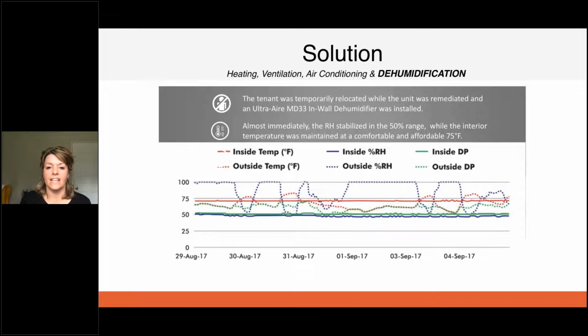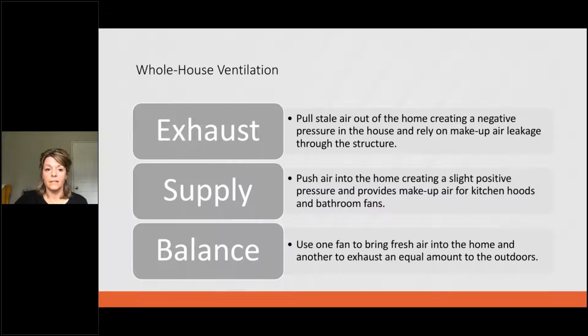What you can see is that solid blue line is the 50% relative humidity we set that dehumidifier to. The dotted line was the RH outside, and you can see there were some pretty wet days there, but the dehumidifier was controlling that to 50% regardless of what was going on outside, and they increased the thermostat temp to about 74 degrees inside, so they're much more comfortable.